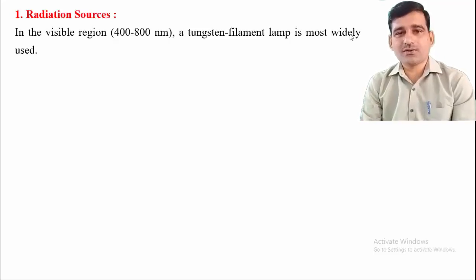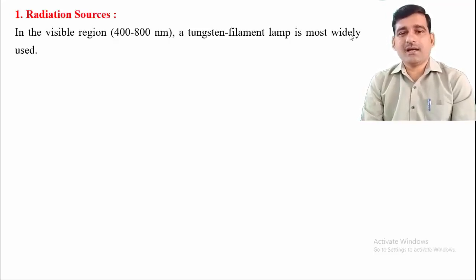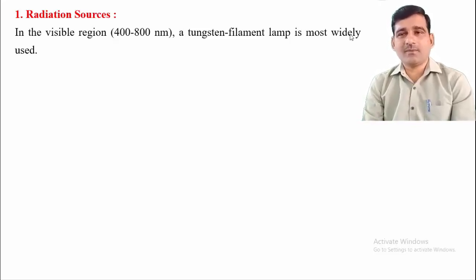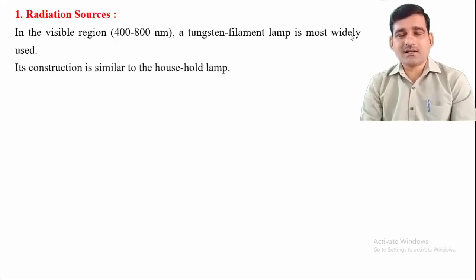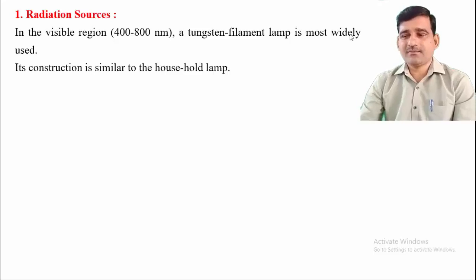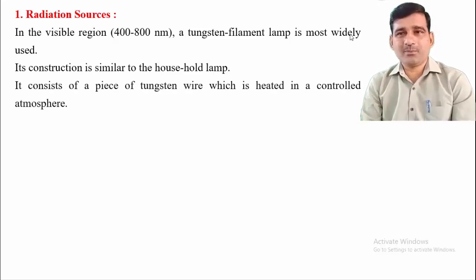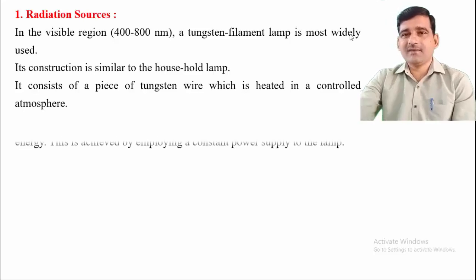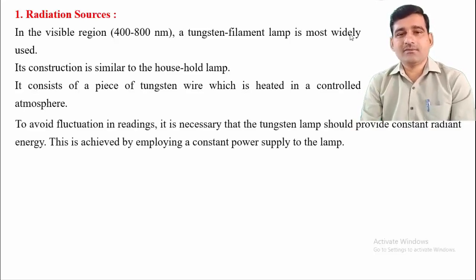The tungsten filament lamp provides light in the range 400 to 800 nm and is most commonly used for the visible region. Its construction is very similar to a household lamp. It consists of a piece of tungsten wire heated in a controlled atmosphere inside an evacuated glass bulb, where two rods are connected by the tungsten wire. When the wire is heated, it provides light in the visible region.